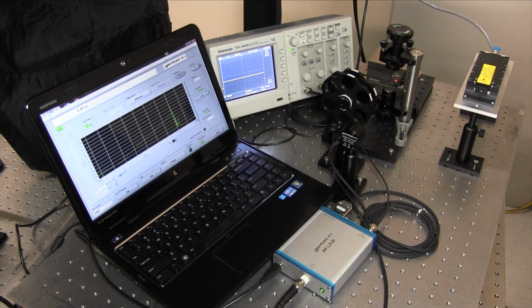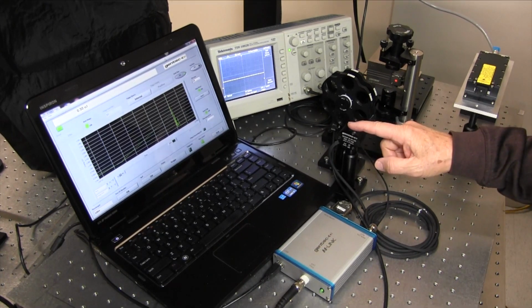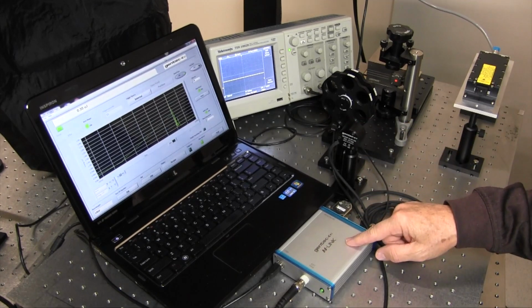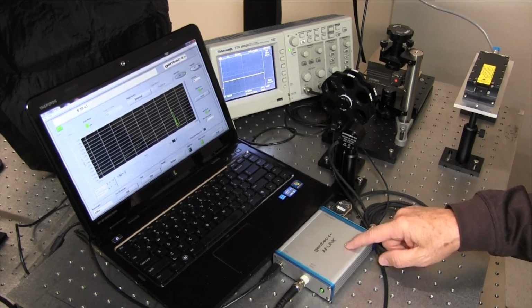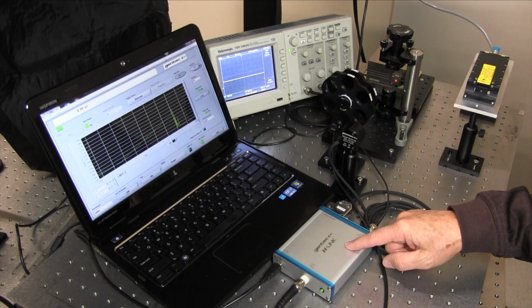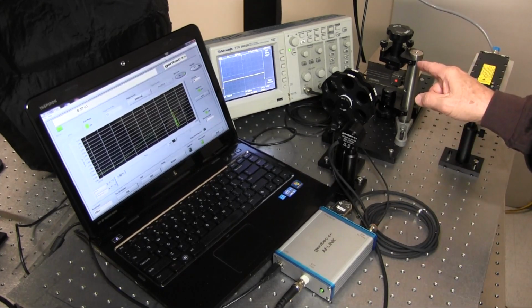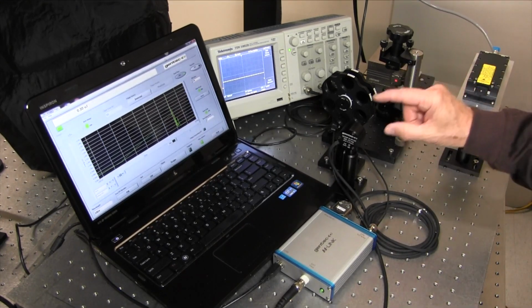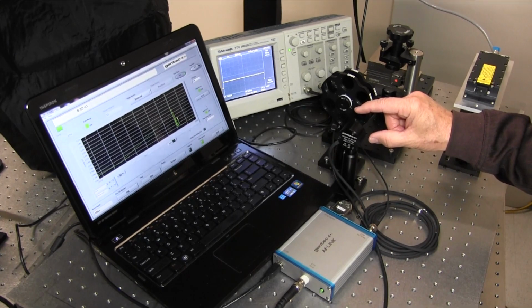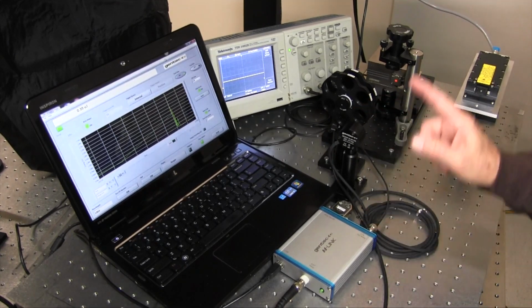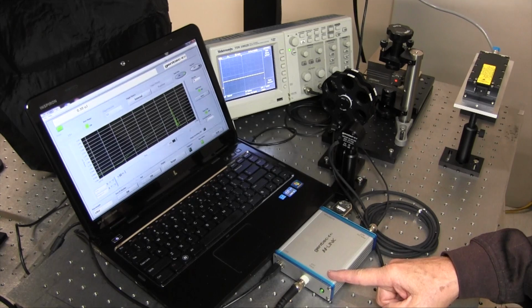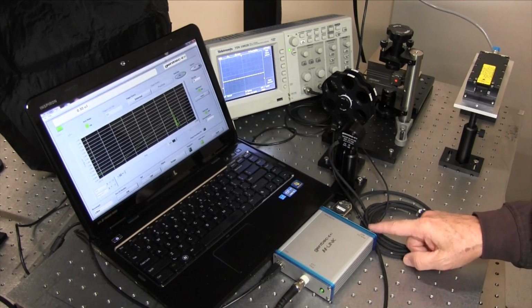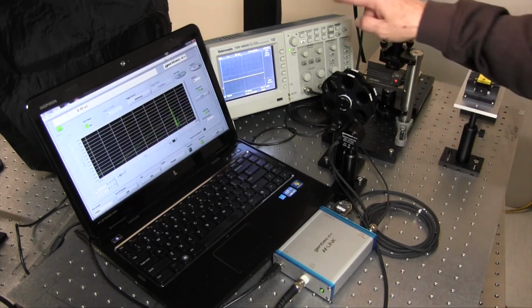I have a QE8 SPB-MT Pyro Joule Meter probe connected to an M-Link running M-Link software on my PC. The probe is set up opposite our neodymium YLF laser, beam centered on the probe. I've connected the sync output from the laser to the external trigger input to M-Link, and I've also connected the analog output of M-Link to our scope.